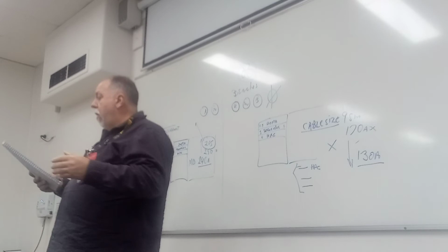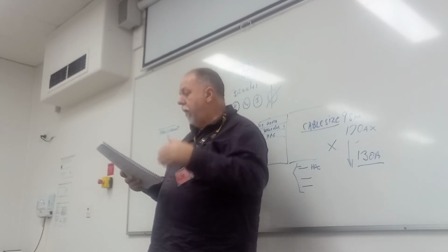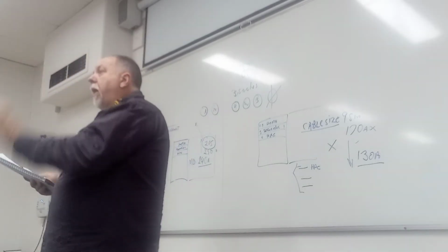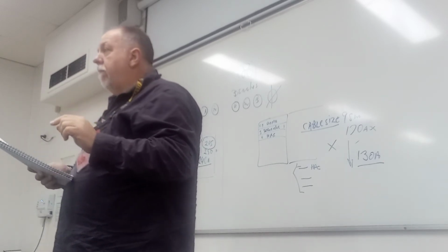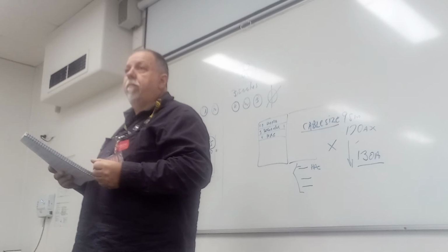All right? The next thing you've got is column 6. Column 6 has the derating table, where it's got like 22, 23 down the end there. They're the ones that you go to when you've got more than one cable. So if I have two cables and I have to work out touching or space between the cables, that is telling me what page to go to. Does that make sense? So for example, I've got two cables in 3.1. I need to go to table 23. Is this making sense? Yeah. All right.